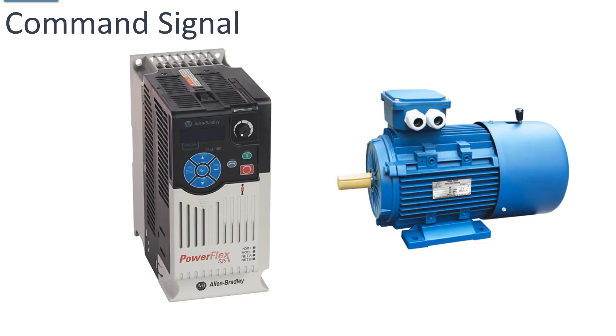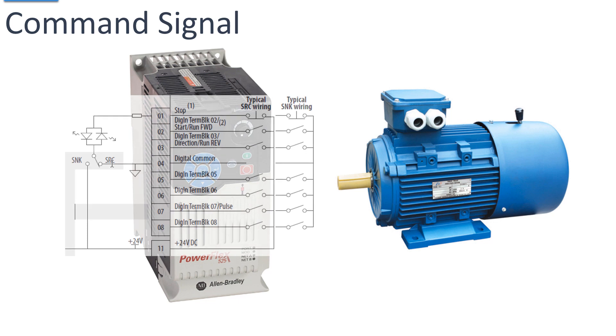Another digital output from a PLC is a command signal. Instead of using a motor starter, you might use a variable frequency drive, which you can use to control the speed of an AC motor. Here is a typical example of connections on that drive — these are all digital inputs; terminals one through eight are digital inputs, and four is a common.